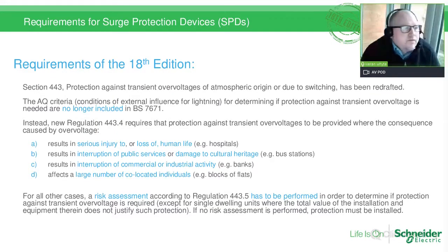So some of the requirements for surge protection, or SPDs, in the 18th edition. Protection against transient overvoltage of atmospheric origin or due to switching, Section 443, has been redrafted. The AQ criteria, which is the criteria we use, when external influences are used for determining if protection against transient overvoltage is needed, are no longer included in the BS 7671.